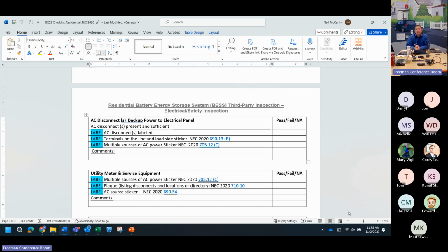If they're not in line of sight, if for example you're forced to put your disconnects on the other side of the house, then you need a plaque. That plaque would tell first responders or whoever where the disconnects are. And because you've put your disconnects away from your meter, you need a plaque at the meter and a plaque at the disconnects.